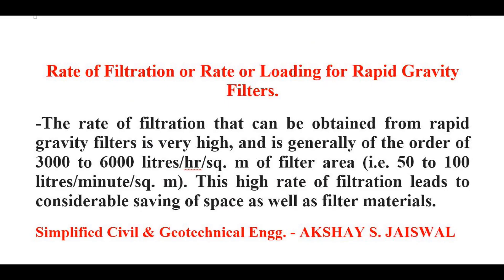Now we will see rate of filtration. The rate of filtration that can be obtained from rapid gravity filters is very high and is generally of the order of 3000 to 6000 liters per hour per meter square of filter area, that is 50 to 100 liters per minute per meter square. This high rate of filtration leads to considerable saving of space as well as filter materials. Rapid gravity filters se filter hokar milne wale paani ki matra kaafi zyada hoti hai. Is high filtration rate ke karan filter materials aur space ki bachat hoti hai.